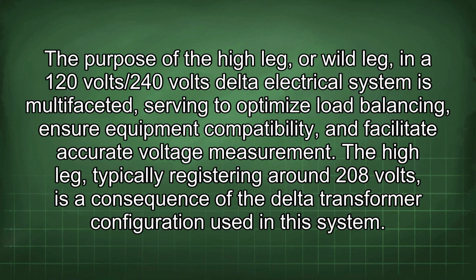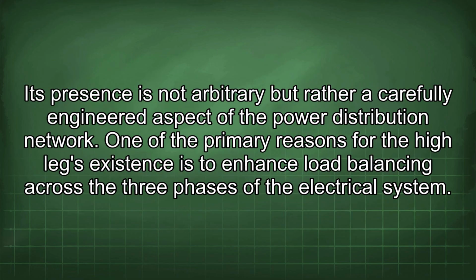The purpose of the high leg, or wild leg, in a 120 volts/240 volts delta electrical system is multifaceted, serving to optimize load balancing, ensure equipment compatibility, and facilitate accurate voltage measurement. A high leg, typically registering around 208 volts, is a consequence of the delta transformer configuration used in the system. Its presence is not arbitrary, but rather a carefully engineered aspect of the power distribution network.